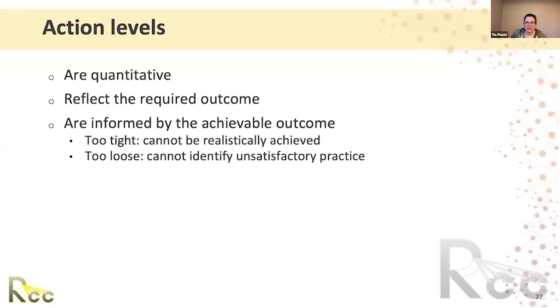However, if you have a machine that's always within 1% of your calibrated dose, setting your action level at 5% might be completely unreasonable, because if it deviated that much, that would be completely crazy. Maybe an action level of 3% is more appropriate, because it would indicate that something was different about the performance of the machine.